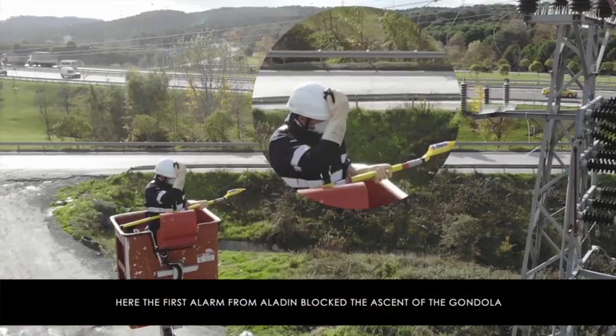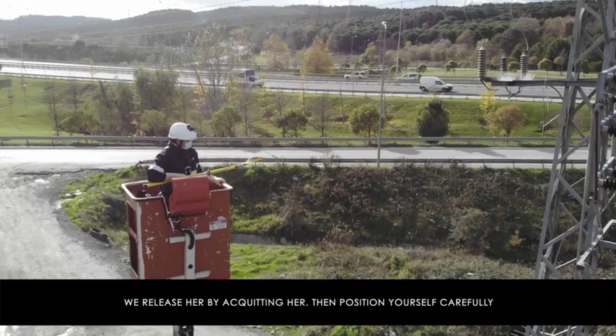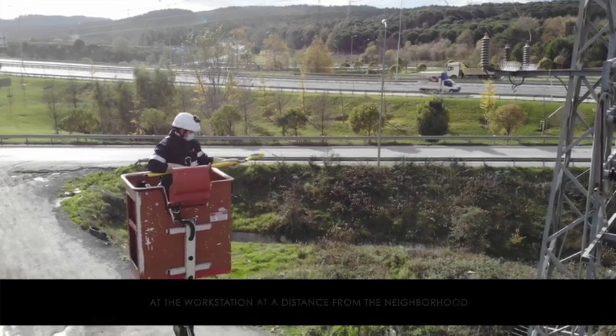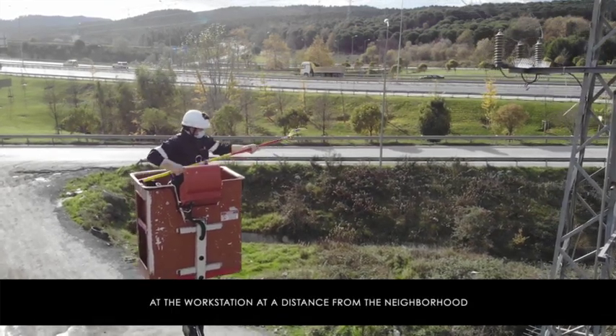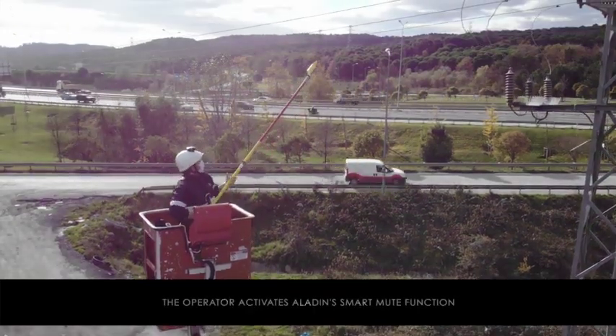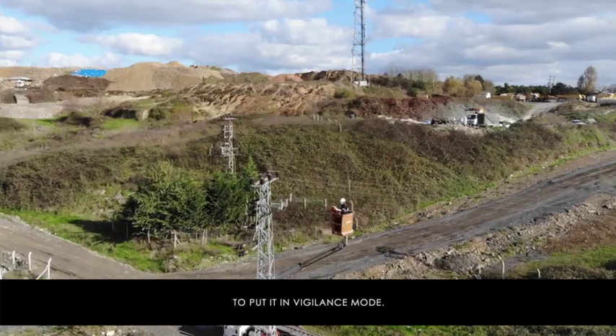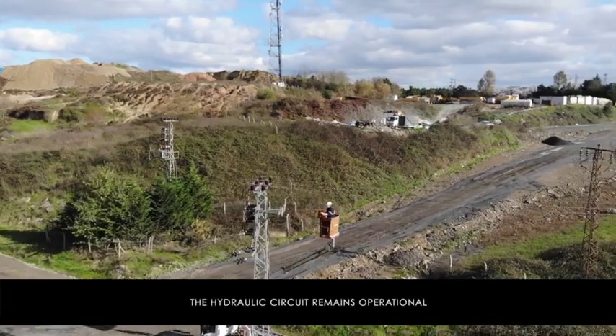Here's the first alarm from Aladin blocking the ascent of the gondola. We release it by acknowledging the alarm, then position yourself carefully at the workstation — at a distance from the hazard — to be able to work without being disturbed by the permanent alarm. The operator activates Aladin's Smart Mute function to put it into vigilance mode.